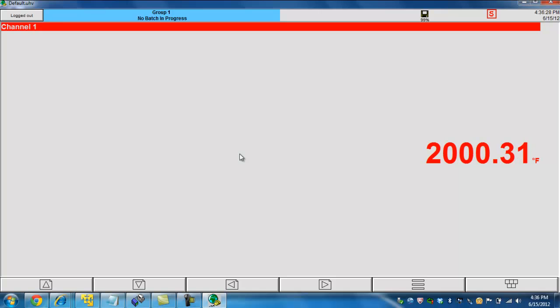So right there alone, we're already meeting our specification of 0.5 degree Fahrenheit accuracy when you use the cold junction compensation. However, in the event that you need even higher accuracy, or if you're using your recorder for an AMS 2750D requirement, you need to calibrate your recorder either monthly, quarterly, or even annually. So let's go ahead and walk through the process of calibrating or adjusting the input channels. It's actually a really easy process to do.